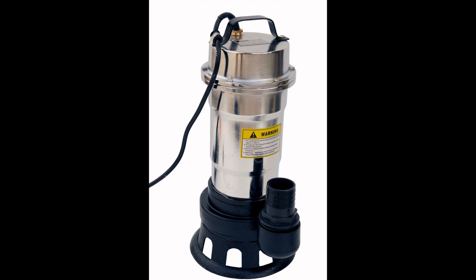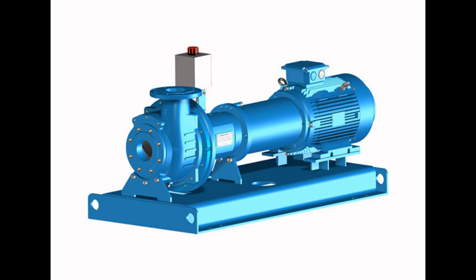The discharge height of the water pump must be approximately 1.15–1.20 times the water lift height. For example, if the vertical distance from the surface of the water source to a water storage tank is 20 meters, then the necessary discharge height of the water pump should be approximately 23-24 meters. This must be taken into account because at the maximum discharge height, the flow rate is practically zero.